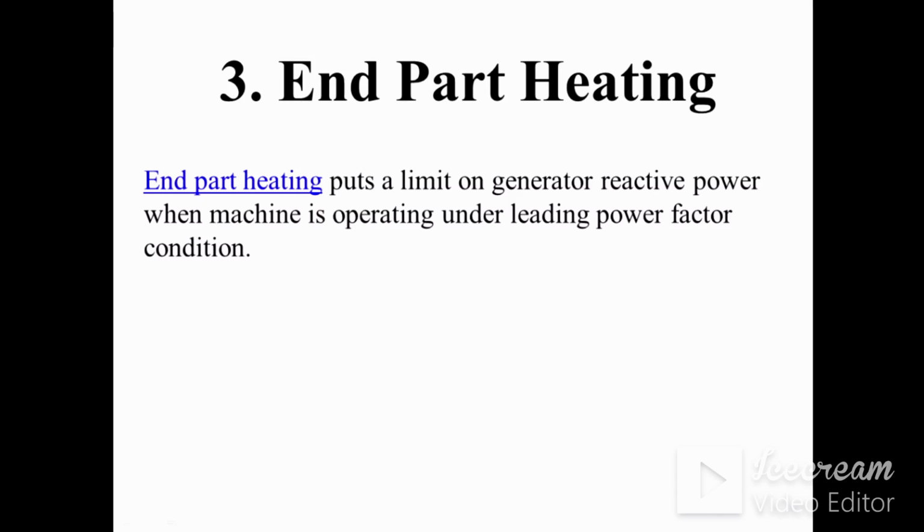Now why we are mentioning the leading power factor is because in the leading power factor condition, generally the generator is under excited, because there are changes in the excitation when it is working under either leading or lagging power factor condition. Suppose we take the example of an overexcited generator. What happens when the generator is overexcited? The retaining ring of the rotor is saturated.